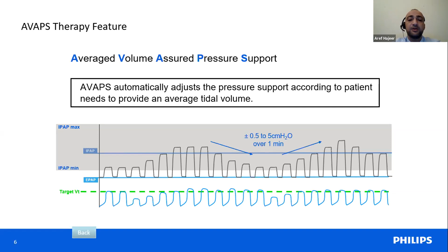Then again, if the tidal volume is maintained normally, the device will always go to the minimal pressure, as long as the tidal volume is stabilized. And then again, if there is something that drops the tidal volume, the device will start to increase the pressure automatically. And we have a setting called Avaps rate or Avaps speed. That range is from 0.5 to 5 centimeter H2O over 1 minute. It's important to mention that the change in the pressure is not breath by breath, it is per minute, so that it will not be an aggressive increase in the pressure to maintain the tidal volume. It gives the patient time to adapt to the pressure increase per minute, as per your setting. So if you set it, for example, to 5 centimeter H2O, it will take 1 minute to increase the pressure from the IPAP minimum by another 5 centimeter H2O.